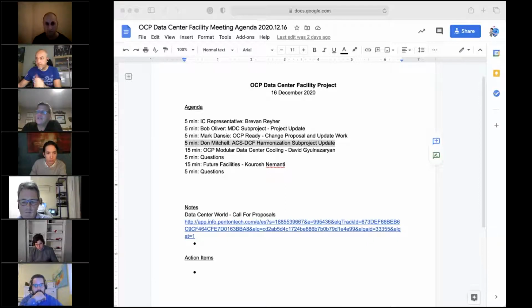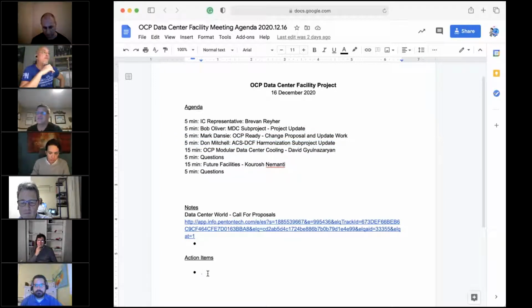So the different spin on this is putting it on the data center owner's responsibility. The stories I've heard are about people adding rear door heat exchangers, not anticipating that the liquid in the rear door heat exchanger—some section of pipe, not the big pipe, but maybe the little piece of pipe that goes down to the IT rack—starts operating below dew point.